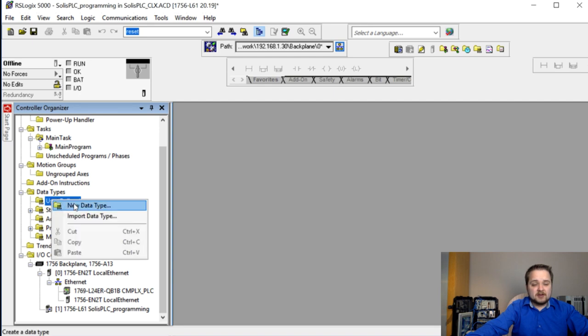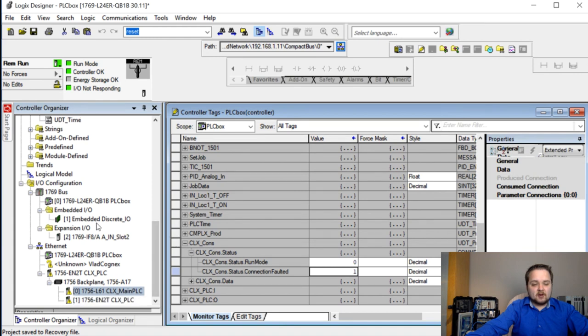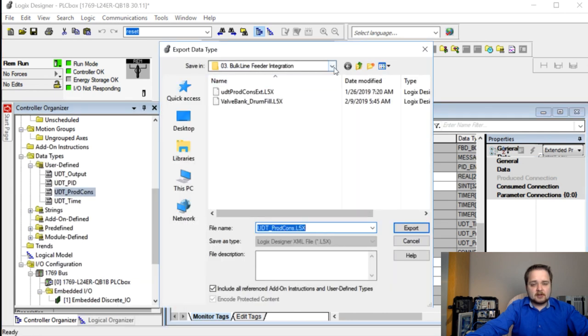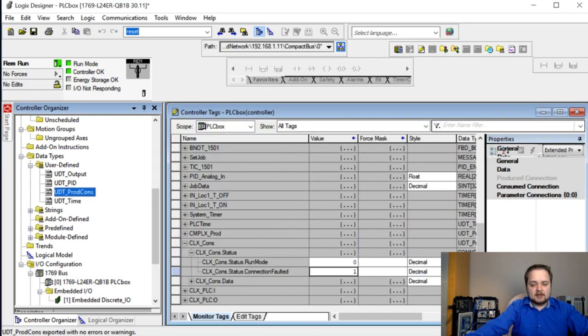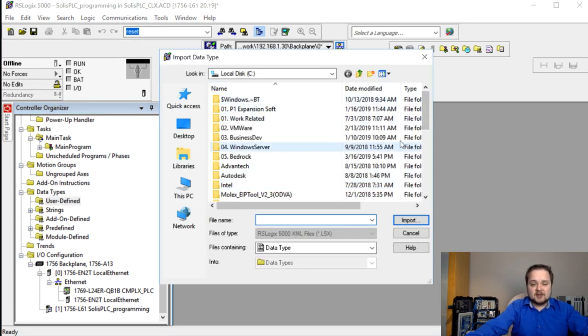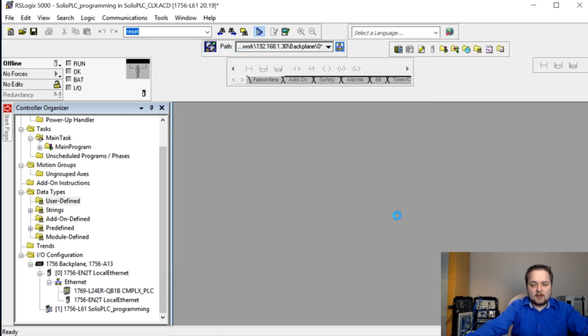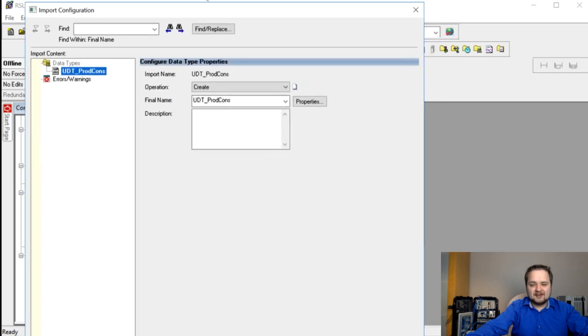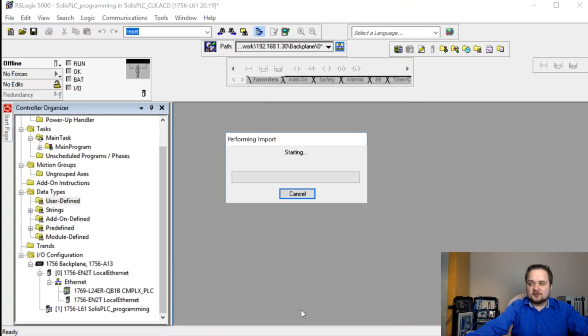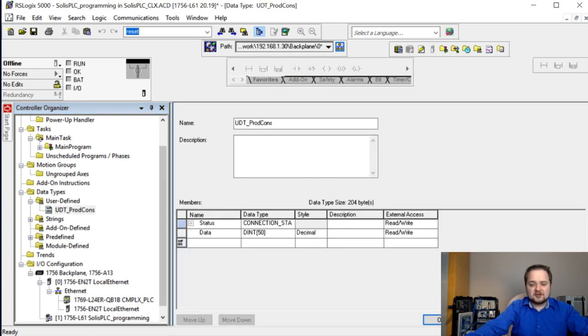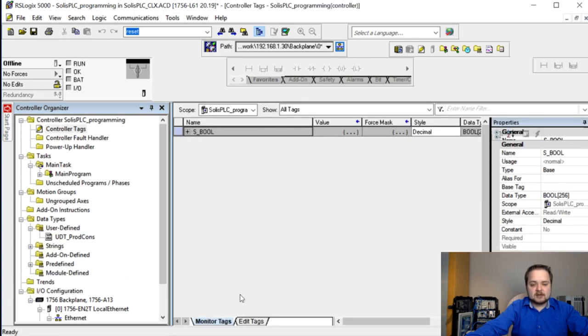We also need to add the same UDT data type to the ControlLogix program. Rather than recreating it manually, I export the UDT from the CompactLogix project and import it into the ControlLogix program. This ensures both controllers use exactly the same structure - a typo in the data type definition would prevent communication. After importing, we can confirm the UDT has the connection status and data members correctly defined.